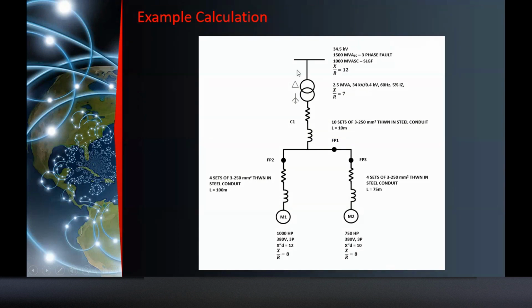Oh, so this is simple, no? But in reality, if you have, let's say, 6 feeders, you will calculate each. Some designers look for the lowest reactance of the system, because that gives the highest fault current. For example, here, this is the highest fault current because my reactance is low. But verify it in the calculation. What some designers do is look for the low reactance, or the highest fault contributor.